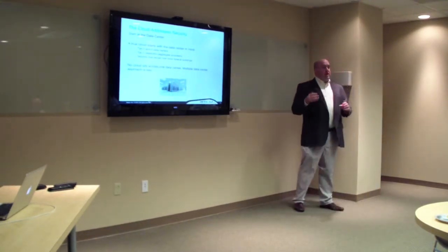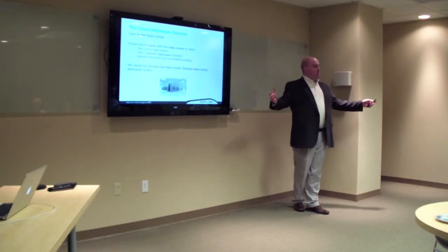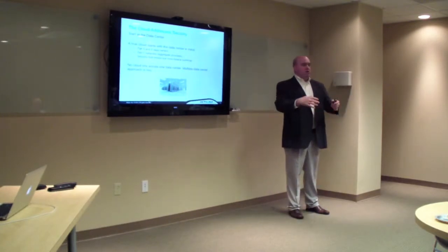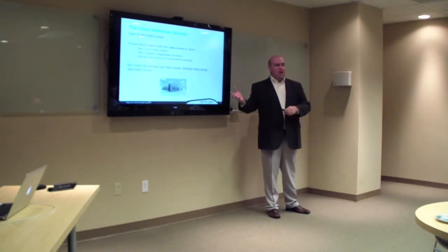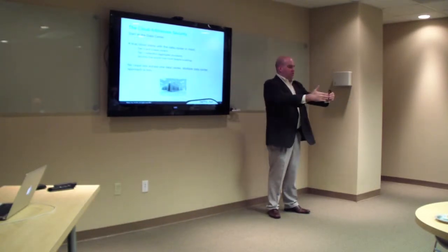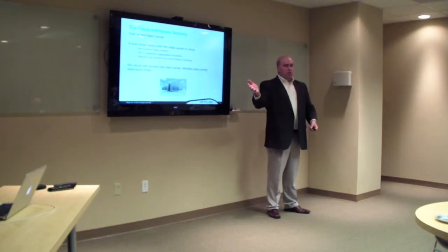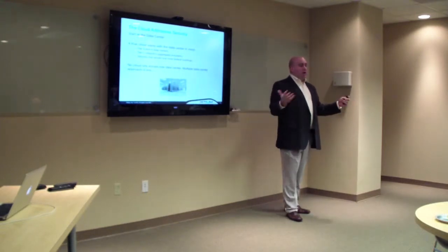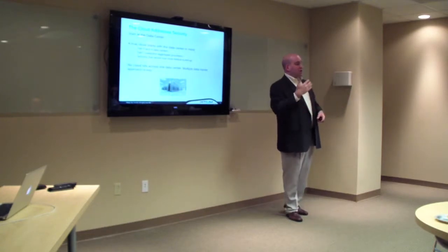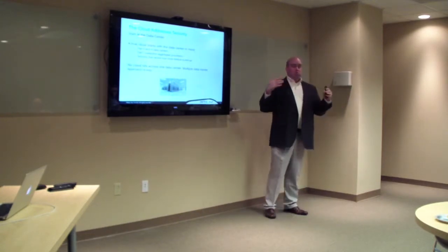Okay, so a Tier 3 data center might have redundancy coming into the facility, but you're stuck at one substation. So if one substation goes down, even if you're connected to another one and it triangulates back, the reality is both of your substations are down in Tier 3. And so you're out of power. So then what do you have to have? You have to have redundancy at your UPS level.